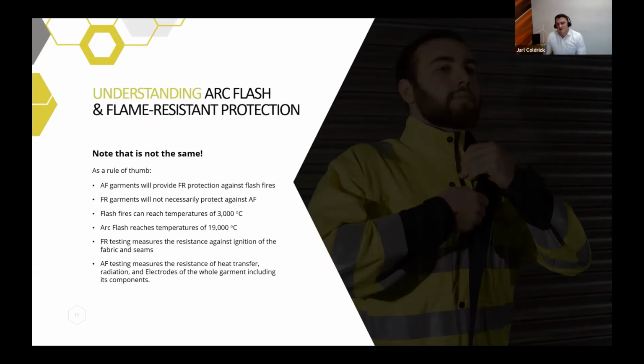The other thing about flame retardant testing is that it only measures the resistance against ignition of the fabric and the seams, whereas Arc Flash testing covers the whole heat transfer, the radiation, the electrodes of the whole garment, and the construction of the garment and its components. That's essential in an Arc Flash because, as we saw earlier, an Arc Flash is likened to a bomb. It can literally tear open garments. So it's essential the components are strong enough and can handle the intense energy from an Arc Flash.